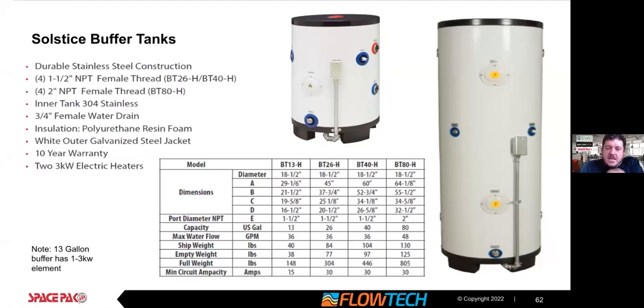The key component, they have electric elements that are on board for use, whether you employ them or not. All the buffer tanks come with electric elements. Our small 13-gallon unit comes with one single 3 kW element. The units from 26, 40, and 80 gallons come with 2 elements. And these elements are great for backup heating. Oftentimes, we're on the cusp of needing 2 SpacePaks on a project, and utilizing these buffer tank elements for backup heat is very important. Perhaps it allows us to not add a second unit outside.